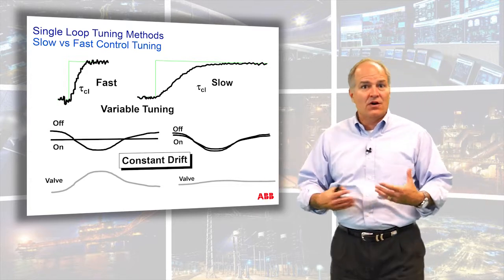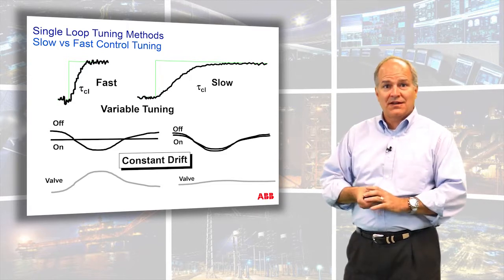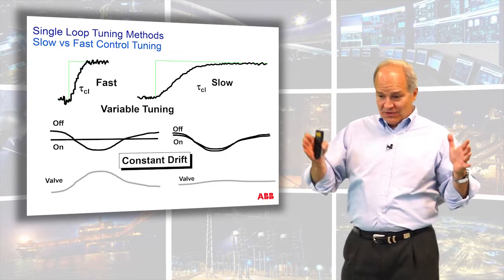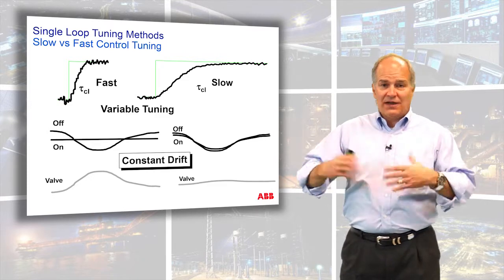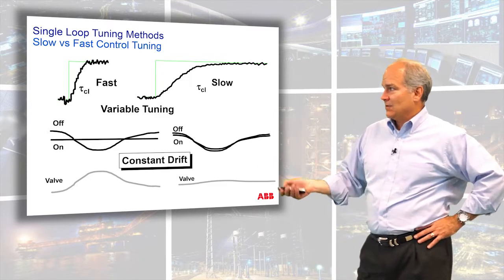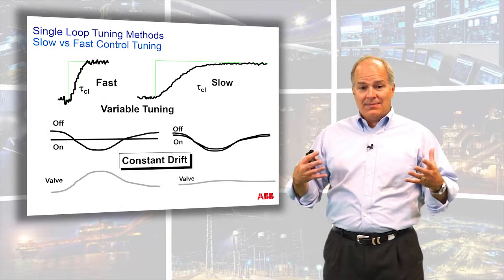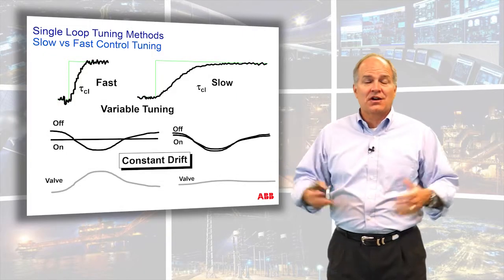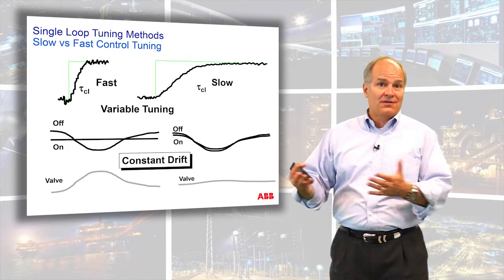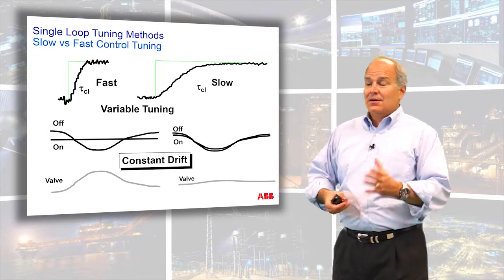That's what a control system is doing all the time. The shock absorber is your actuation device. If the road is moving slow enough, you don't feel it. If it's too fast, it passes through and you feel it. On the slow-tuned side, even though it's the same disturbance, it's now too fast for the control to deal with. So when control tries to deflect the energy into the valve, the valve doesn't move, and the off-control and on-control process response look about the same.